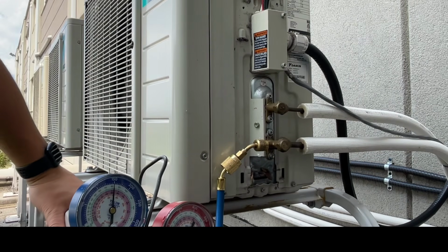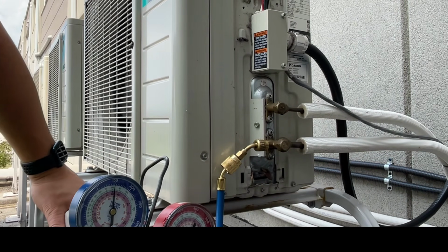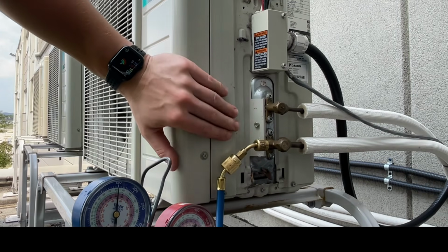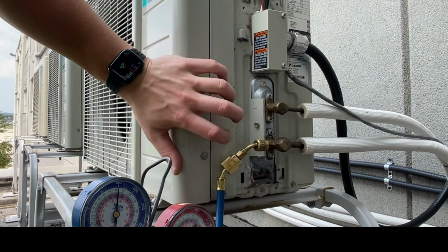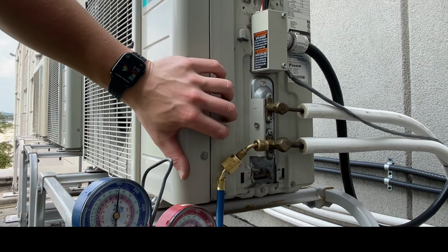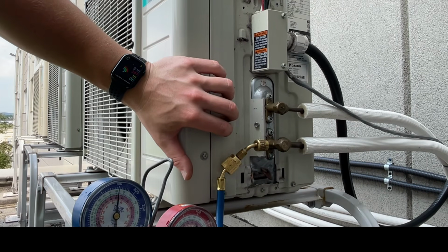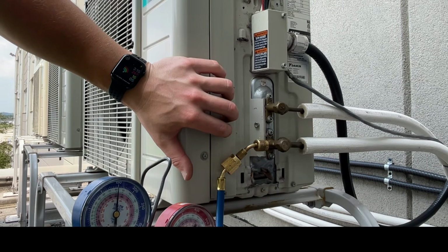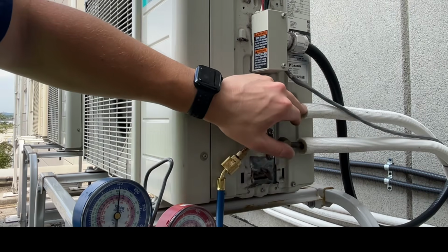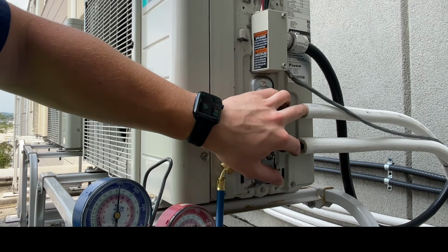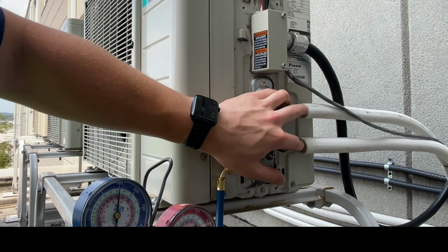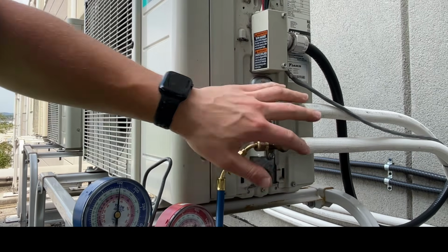And that's what changes our pressures and temperatures in our system. Anyways, that's inside the machine here. In your standard central AC system, the metering device is indoors. So that's why you have to insulate both lines, because both of these pipes are cold and they both sweat, and you can lose efficiency if they're not insulated.